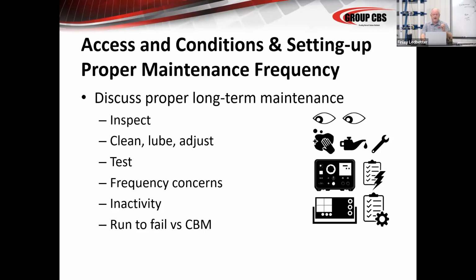The frequency and inactivity are a killer. Ask a breaker to hold as tight as it can for many years. You're asking it to hold 1,000 foot-pounds of pressure and then to react like the day it was new. That's difficult for any mechanical system to do. You're asking a breaker to close with 1,000 foot-pounds of pressure. John, I would stand up on this chair and try to do it like you used to, but I know I'll fall off of it. 1,000 foot-pounds of pressure, 5 years, then react in milliseconds. That's what you're asking your switchgear to do. In a dirty environment, near the ocean, with poor lubrication, it's not going to do it.